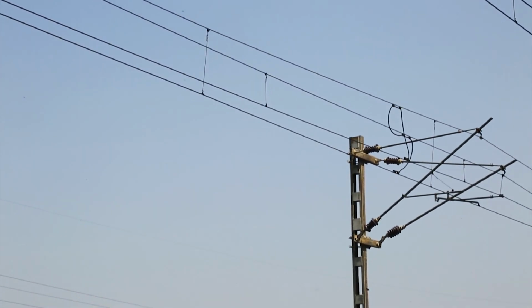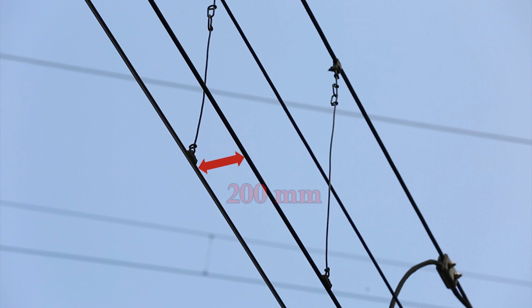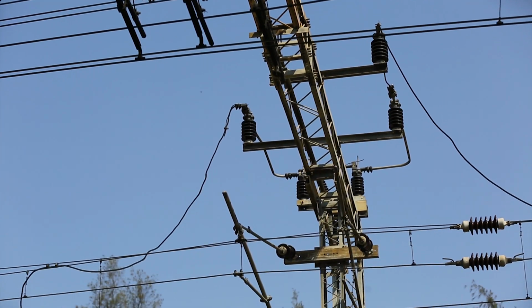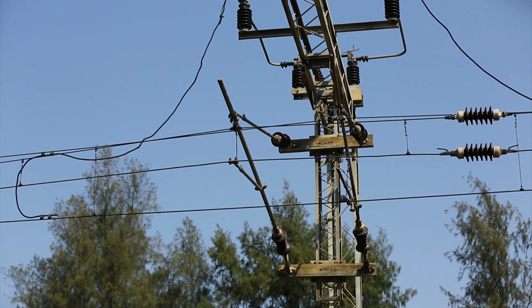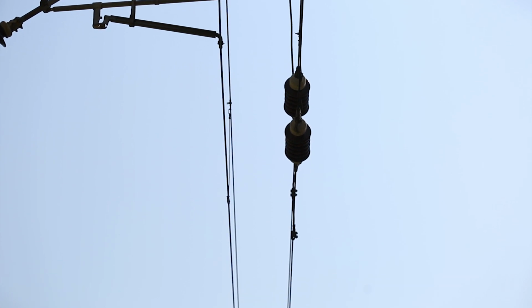Overlap. The continuity between two consecutive tension lengths is maintained by an arrangement which is known as overlap. Gap between two parallel running contact wires at an uninsulated overlap: 200 mm. Gap between parallel running contact wires at an insulated overlap: 500 mm.